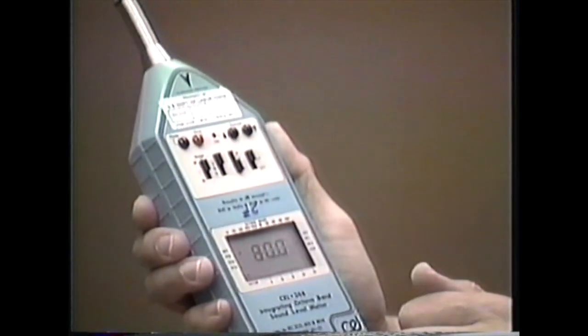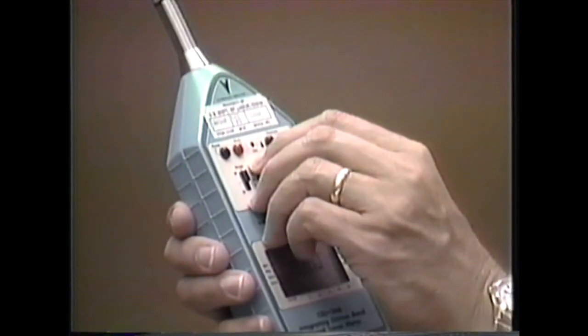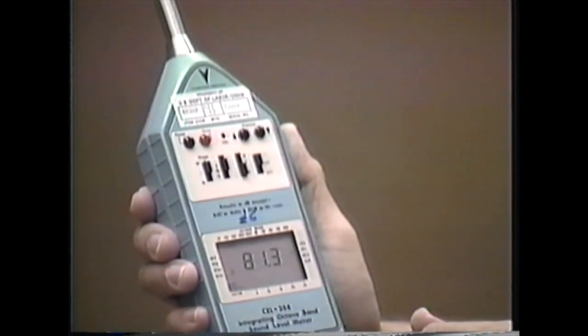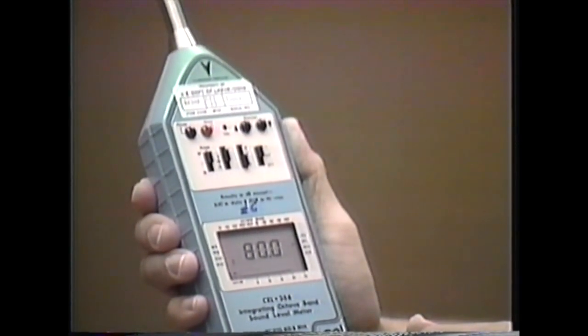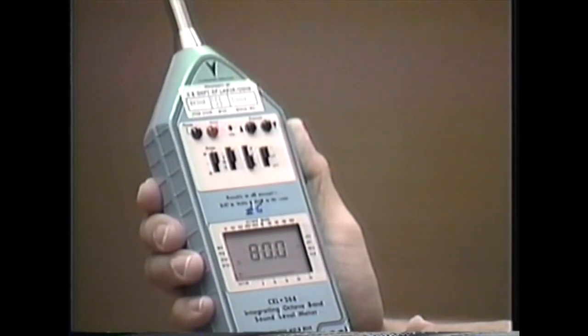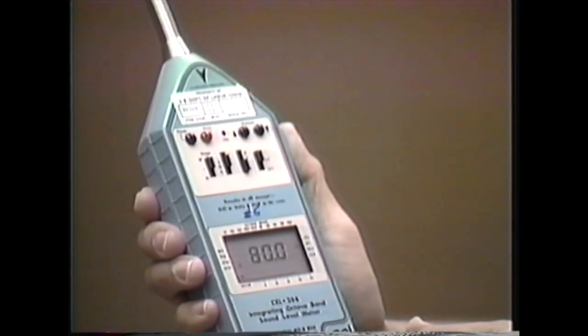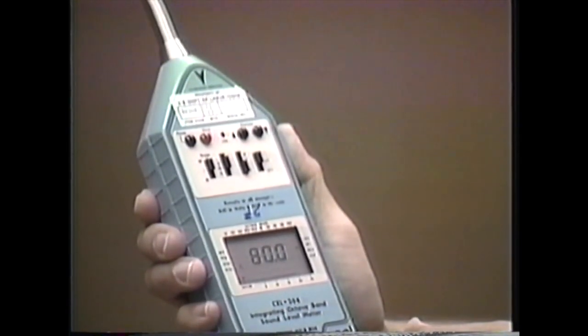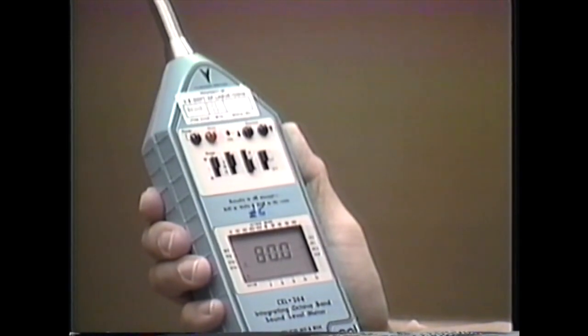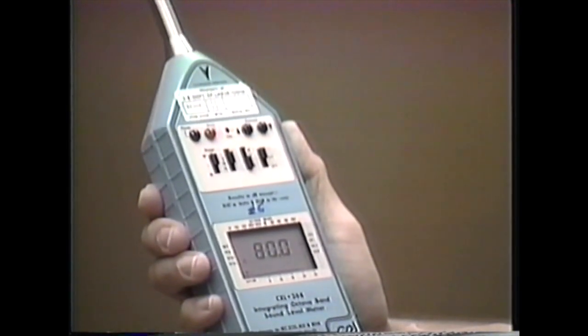The Type 1 instrument gives us a little more flexibility than the screening instrument, in that the Type 1 instrument can be used to help fill out the OSHA 92 form, where we get A slow as required by the standard, and also C slow, Charlie slow, as supporting backup readings, which help us do frequency analysis or give us some idea of the type of noise pattern that we have. In addition to helping us with the OSHA 92 form, this can be used to do octave band analysis and peak analysis. We'll take a moment to look at both of these.